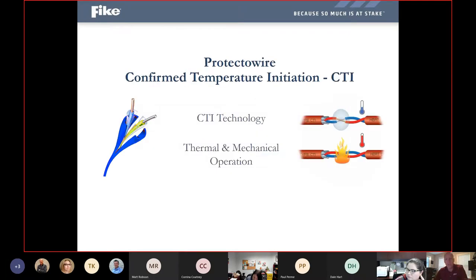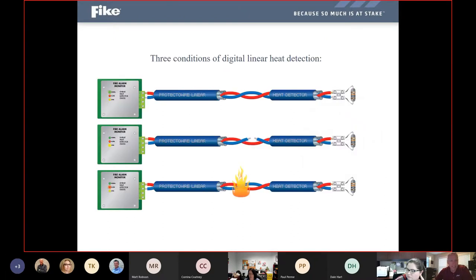And one of the real neat things about the advancements in this technology is something called confirmed temperature initiation. So as soon as those wires melt and come together, they would historically have indicated an alarm. But now with this confirmed temperature element, that's not enough. Once those wires touch, it sends a signal out to the wires to actually read the temperature where that short has occurred. If that temperature is still considered ambient or within the realm of normal operation as programmed, it will not go into alarm. It'll just go into a fault because maybe a fork truck or a box was put up somewhere and it actually pinched the wire. So there's not a heat increase there, but the wires have touched. So it's more of a wire short or a trouble condition versus an actual alarm from a fire.